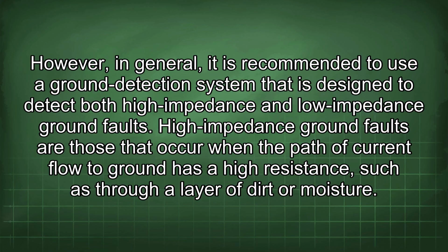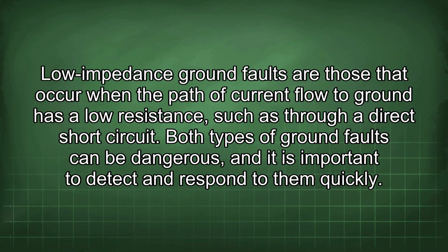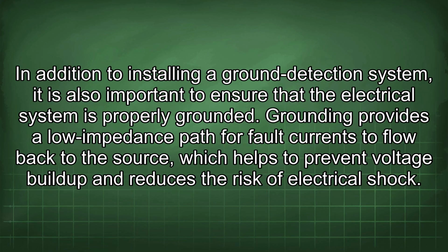High impedance ground faults are those that occur when the path of current flow to ground has a high resistance, such as through a layer of dirt or moisture. Low impedance ground faults are those that occur when the path of current flow to ground has a low resistance, such as through a direct short circuit. Both types of ground faults can be dangerous, and it is important to detect and respond to them quickly. In addition to installing a ground detection system, it is also important to ensure that the electrical system is properly grounded. Grounding provides a low impedance path for fault currents to flow back to the source, which helps to prevent voltage buildup and reduces the risk of electrical shock.